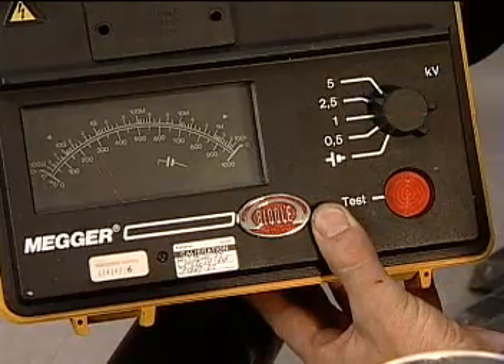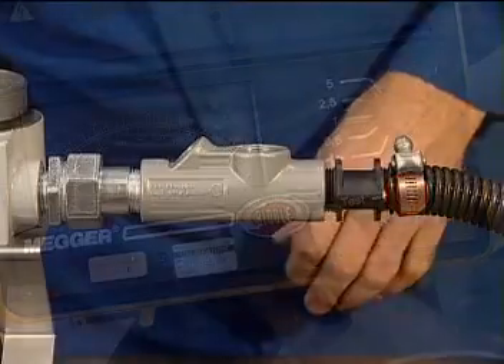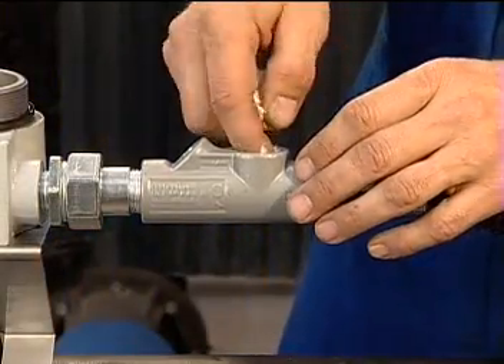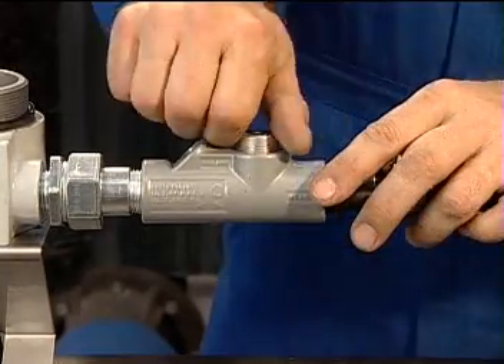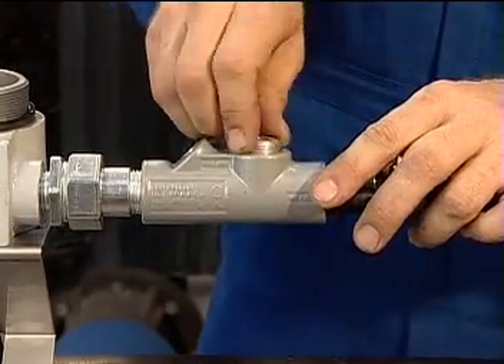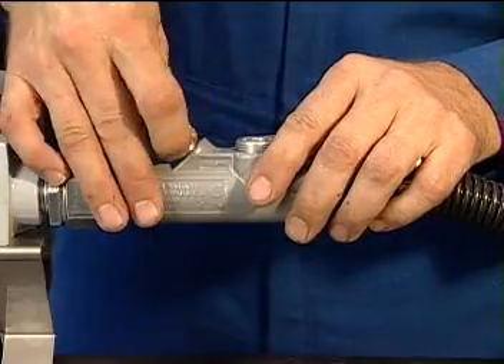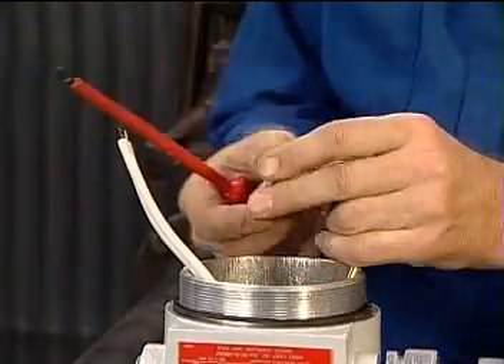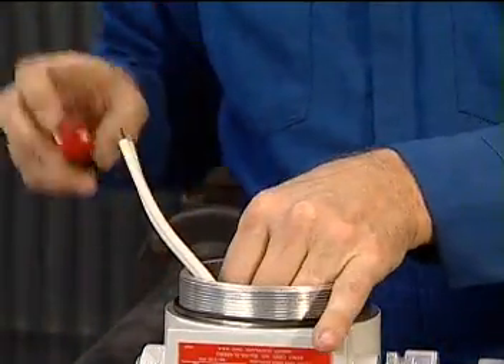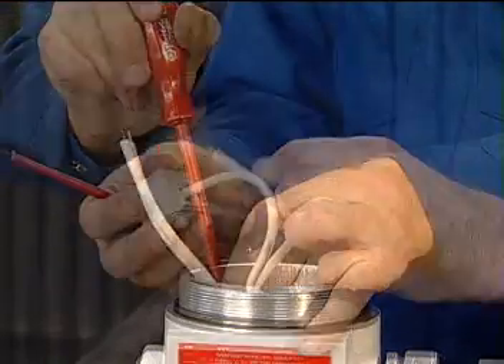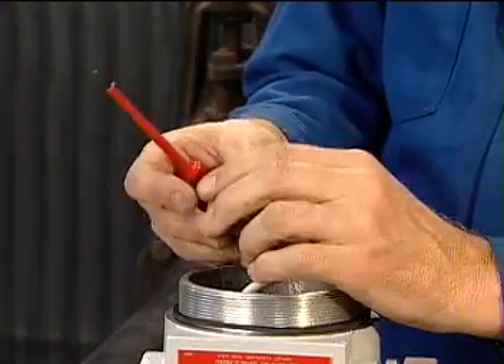After final insulation resistance testing has been performed, pack the fiber provided into each end of the sealing fitting to form a dam. Mix and pour the sealing compound into the fitting and install the plugs. Then, connect the braid to the grounding bar and fasten it inside the box. Connect the bus wires to the terminal block provided.